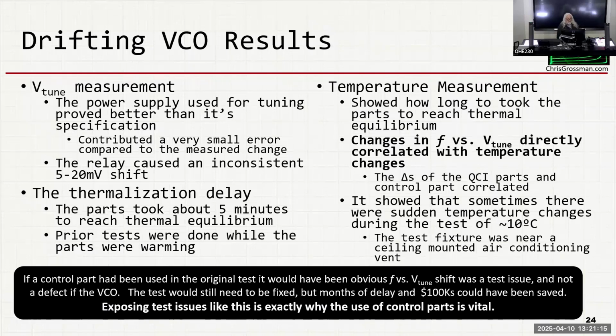All the deltas of both the QCI parts and the control parts were correlated with temperature, and it was shifting. It turns out that sometimes there were sudden changes during the test of about 10 degrees, and it's because it was near an air conditioning fixture that was blowing on it. Wow.